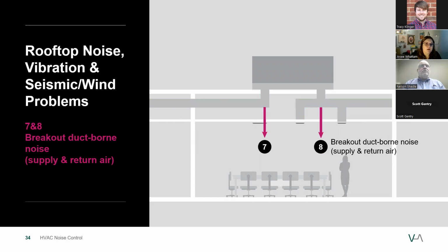Next would be breakout ductborne noise. Duct breakout noise is sound transmitting through light gauge ductwork and into occupied spaces. This is the noise path that is most often overlooked in HVAC noise control design. Standard silencers can't guarantee to solve this problem because an analysis is required to figure out how much breakout will require and where. This noise path is probably the most common cause of noise problems for designs that already have some sort of noise control measures in place.